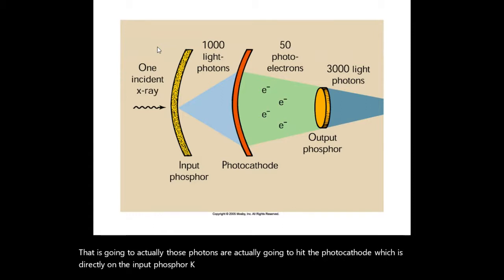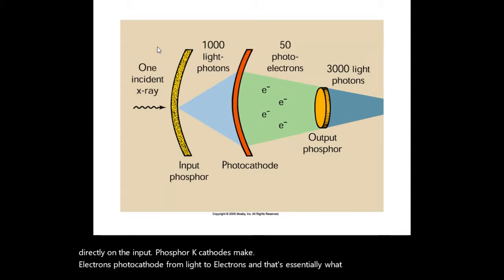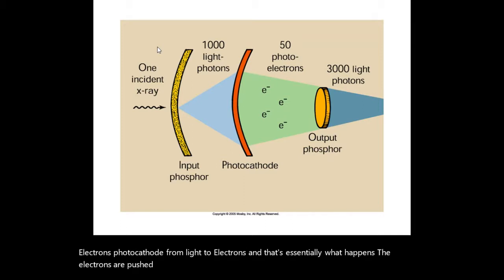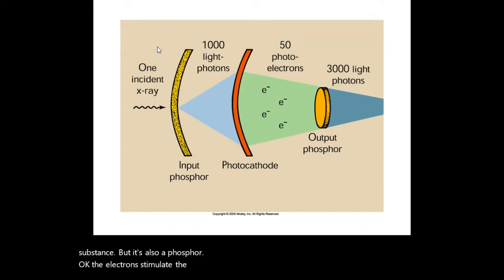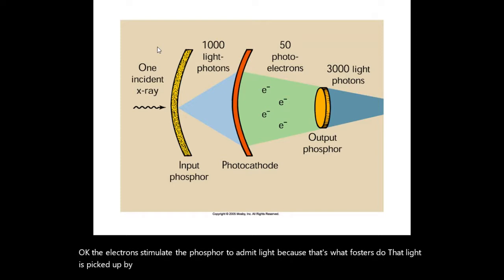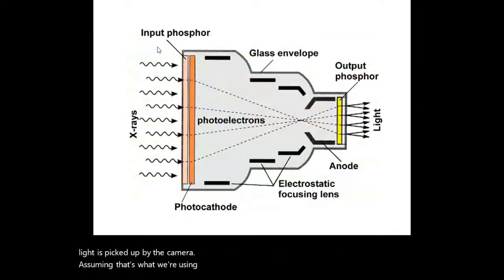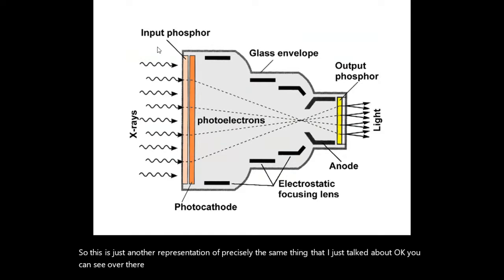Cathodes make electrons, and that's essentially what happens. The electrons are pushed across the image intensifier tube, and in turn are going to strike another substance, which is also a phosphor. The electrons stimulate the phosphor to emit light, because that's what phosphors do. That light is picked up by the camera, assuming that's what we're using. So this is just another representation of precisely the same thing I just talked about. You can see over there to the left where the X-rays are coming in.